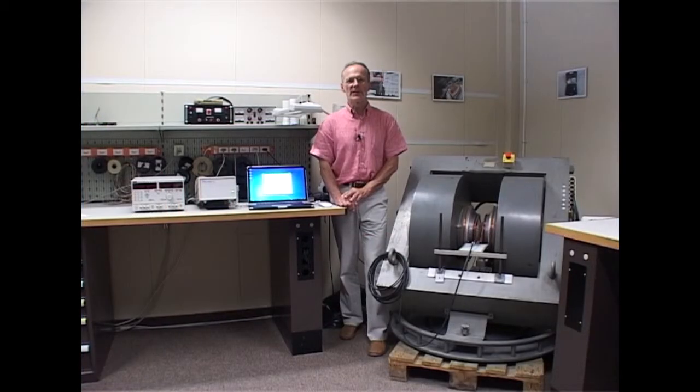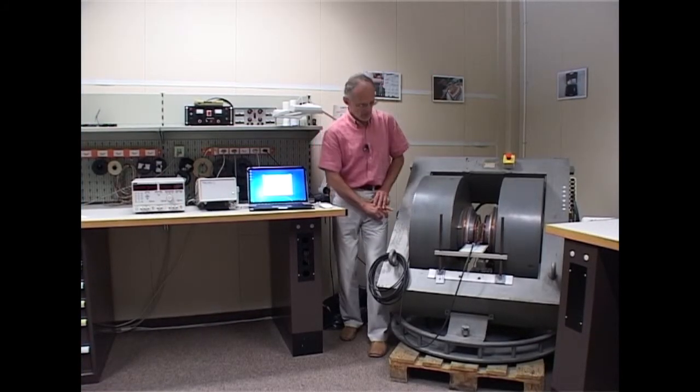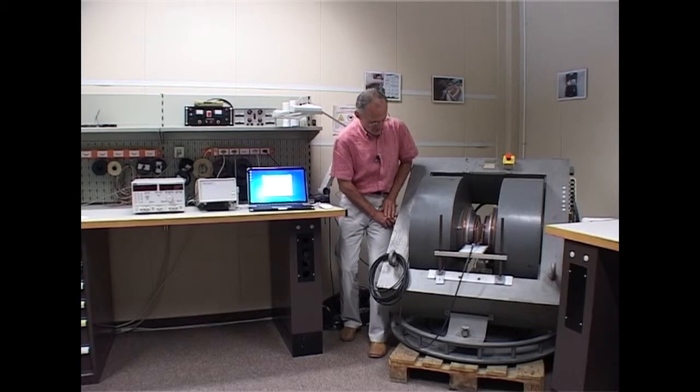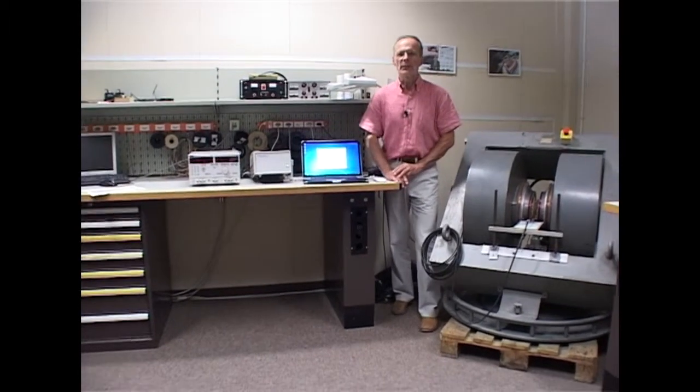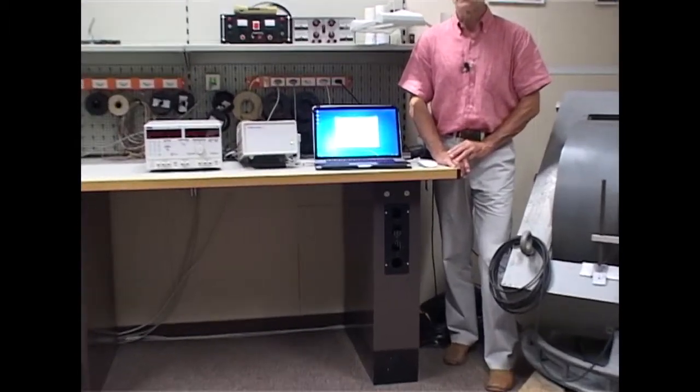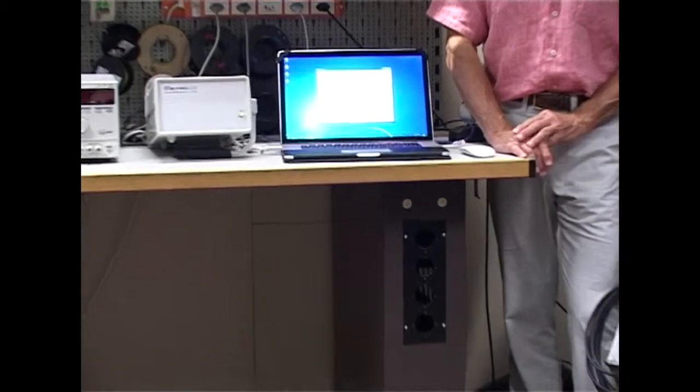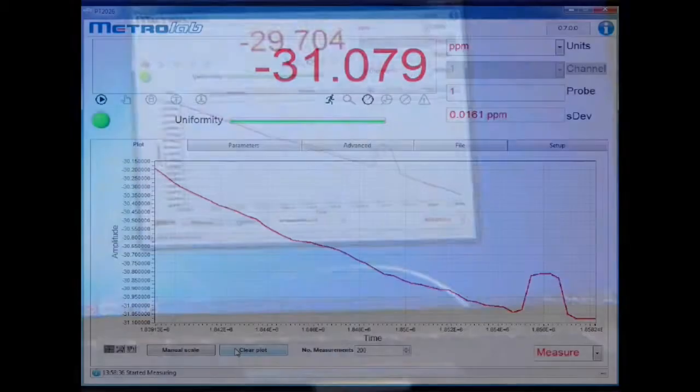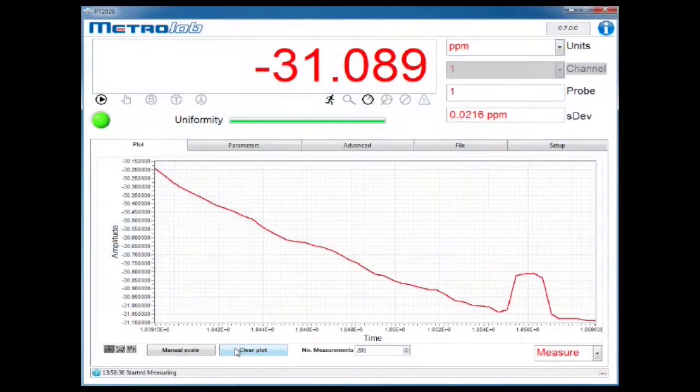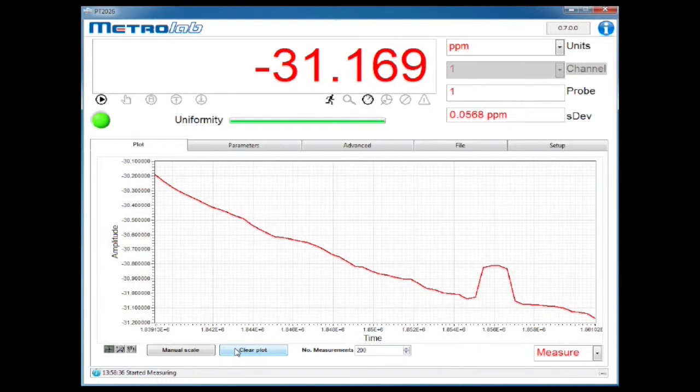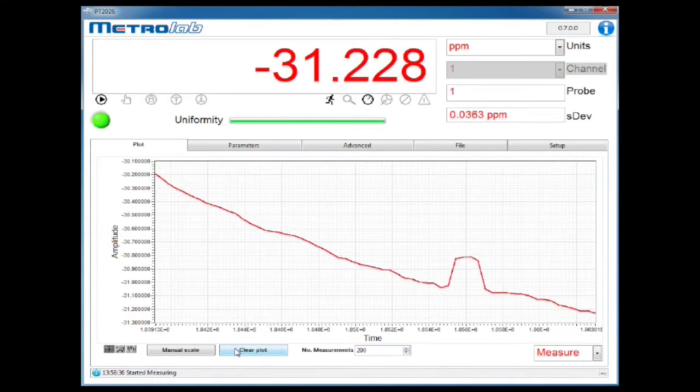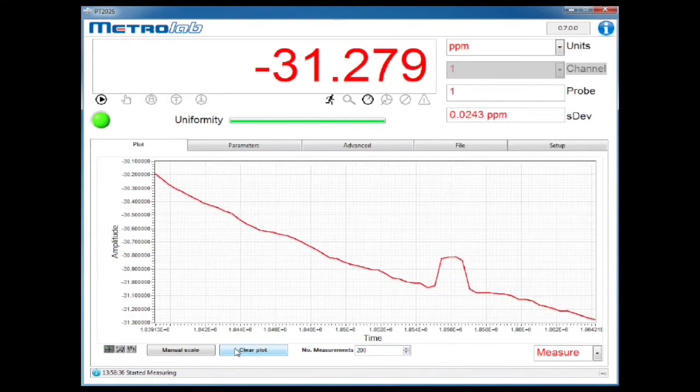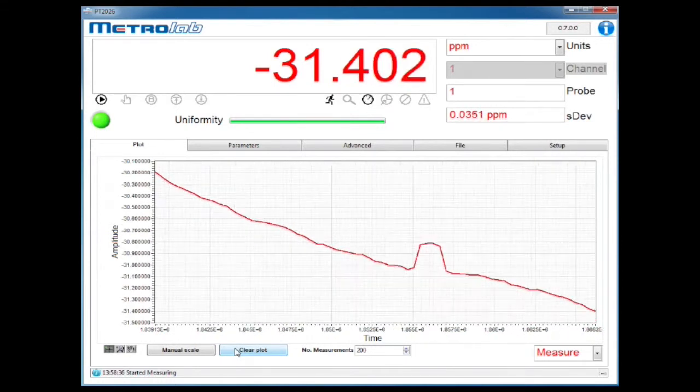Here we can repeat our sensitivity experiment. I just press on the yoke, and we can see that even a weakling like myself can deform a magnet this size. Of course, given the magnet's size and the forces involved, the effect is much smaller, only on the order of 0.1 to 1 ppm, but it's still clearly detectable.